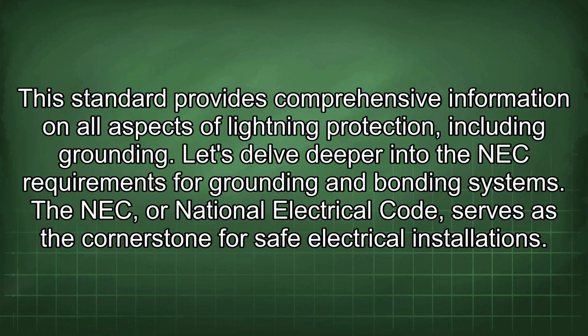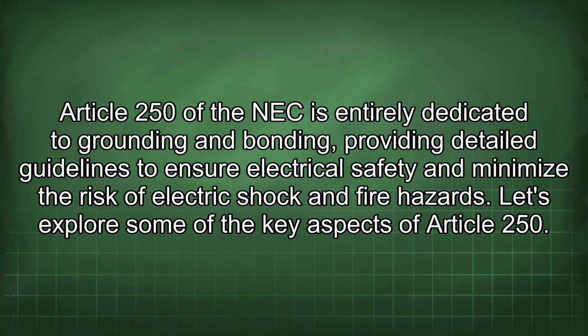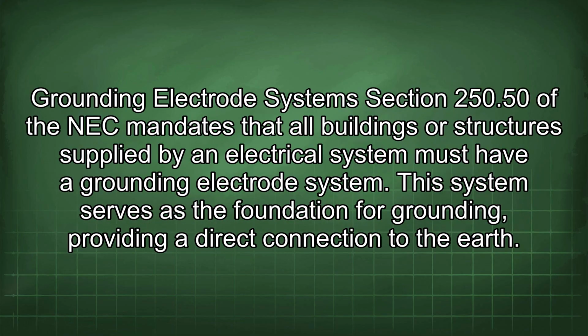Let's delve deeper into the NEC requirements for grounding and bonding systems. The NEC, or National Electrical Code, is the cornerstone for safe electrical installations. Article 250 of the NEC is entirely dedicated to grounding and bonding, providing detailed guidelines to ensure electrical safety and minimize the risk of electric shock and fire hazards. Let's explore some of the key aspects of Article 250. Grounding electrode systems. Section 250.50 of the NEC mandates that all buildings or structures supplied by an electrical system must have a grounding electrode system.